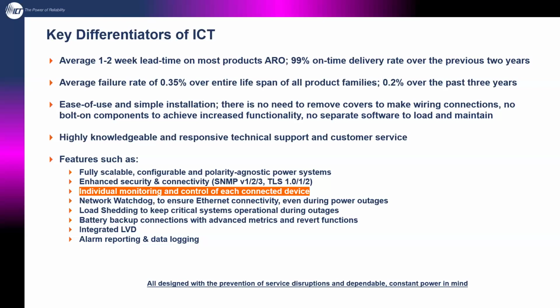This orange one here is what separates us from all the other animals at the zoo - that ability to individually monitor and control each connected device. Whether it's radios, routers, switches, or whatever equipment you've got connected to an ICT power plant, you can get readings, set settings, cycle power, make adjustments, and get alarms down to that granularity. If something goes wrong with load number 4 but everything else is fine, you can focus just on load 4 without affecting other equipment. That ability to avoid bringing systems offline to make adjustments or repairs is invaluable - no one's getting phone calls from angry customers who've lost connectivity because you had to shut the whole thing down to fix something.